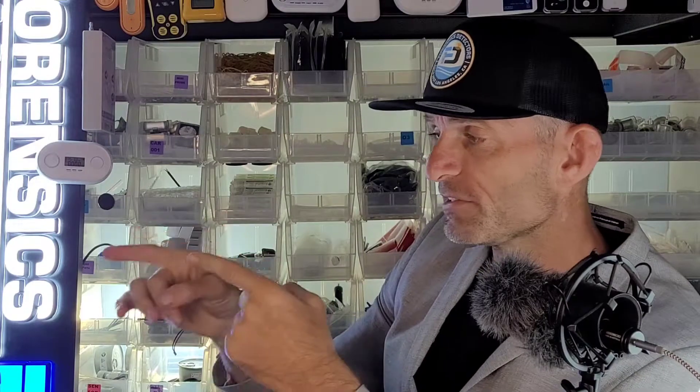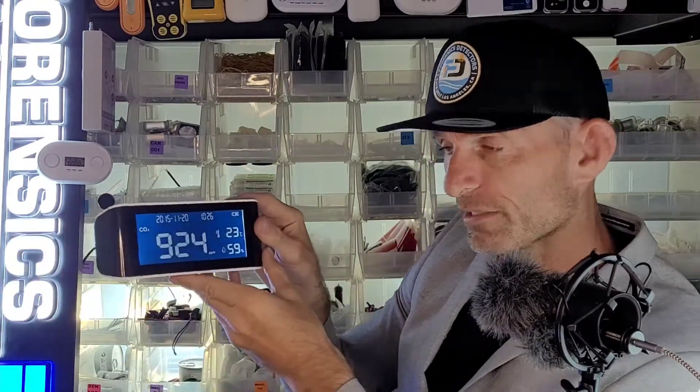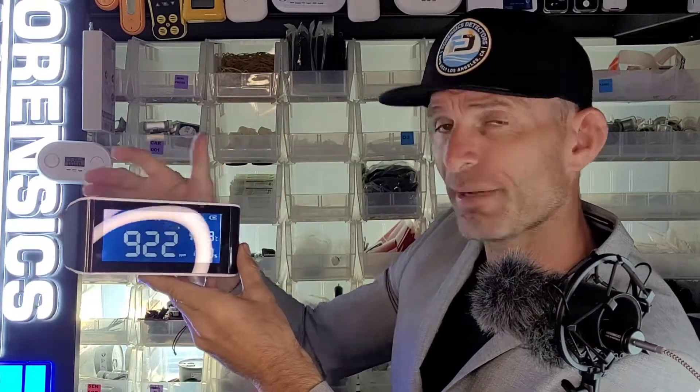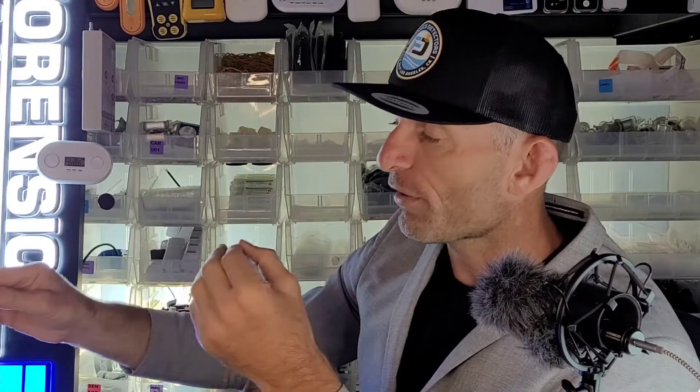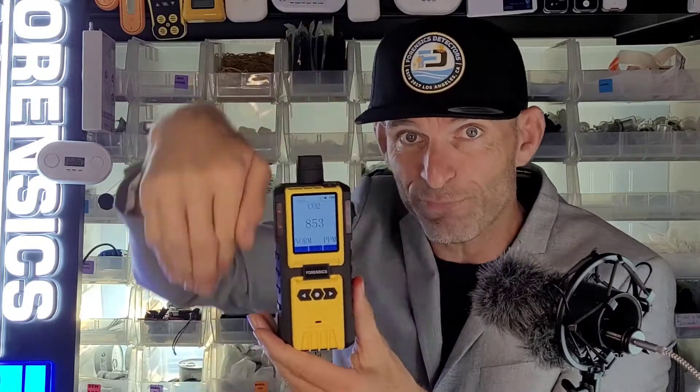Now don't forget, these little units are made to be passive. The molecules are diffusing and slowly come onto the sensor, so the speed of measurement is not really a priority in that case. However, we have a micro pump here — the gas is forced onto the sensor.